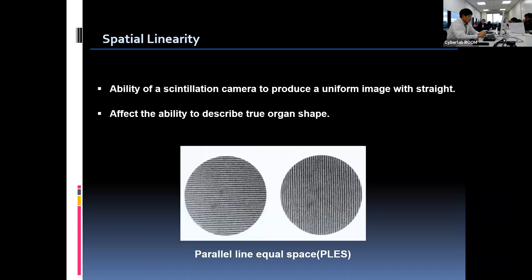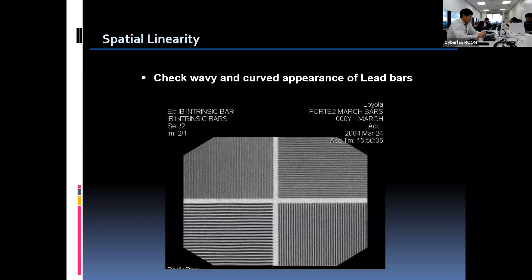The next procedure is the spatial linearity test. Spatial linearity refers to how well the camera produces images with straight lines — it is an important factor for describing true organ shape. These images are obtained with a parallel line equal space phantom where all lead bars and spaces have the same widths. Deviation from straight lines should be less than 1 millimeter. Linearity testing can be done along with resolution testing using the four-quadrant bar phantom. We check the straightness of parallel bars and review the image to see if there is any wavy or curved appearance.